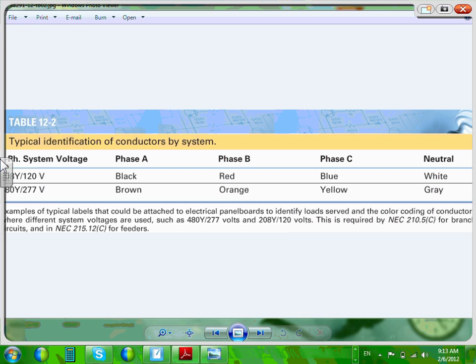Color coding. This is very interesting. Color coding, guys, right here. Color coding for the two systems, 208, 120, and 480. These are very interesting. Brown, orange, yellow, and gray, and please, black, red, blue, and white. They're not code. They're color-coded industry standard. So if you see a brown, orange, yellow, gray, most likely this system is 480, 277. If you see black, red, blue, white, most likely this system is what? 208, 120. Though, a couple of things you have to understand.